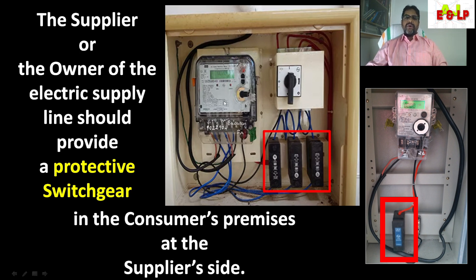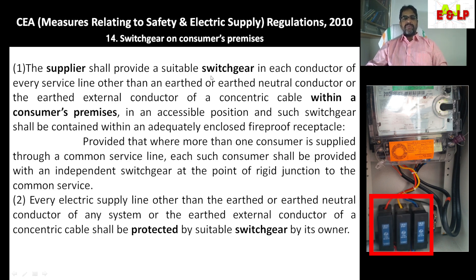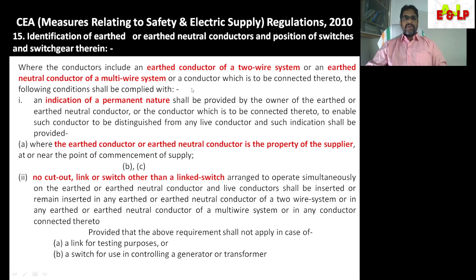To the supplier side of the connection, there must be a protective switchgear. We have our safety regulations, CEA, which relates to safety and electric supply. According to Regulation 14, second clause, there must be a switchgear provided by the supplier before the point of commencement of supply, and it should be of protective type. In short, there must be a protective switchgear provided at the consumer premises by the supplier.